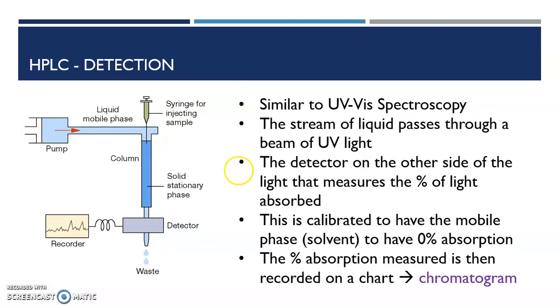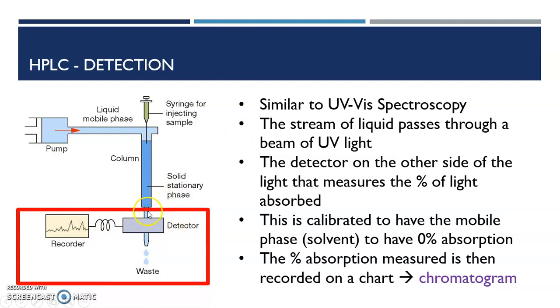And the detection part is basically here. Once the substance comes out, there's a detector, and then it goes to a recorder, which produces a chromatogram. It's a little bit similar to UV-vis in the detector. It's basically a stream of liquid passing through a beam of UV light. The detector on the other side of the light measures the percentage of light absorbed. And this is calibrated to the mobile phase, so that the mobile phase will have zero absorption, and then all the other substances in the mobile phase that come out from here will have their own absorption. That absorption creates that chromatogram.